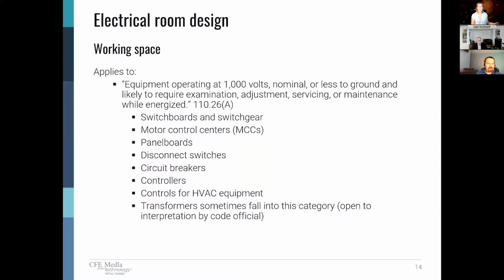So where does the working space requirement apply? Well, 110.26(A) tells us that equipment that's operating at 1,000 volts nominal or less that is likely to be examined, adjusted, serviced, maintained while energized. And that's really the takeaway. That's the part that should probably be underlined and bolded, is the while energized piece. And in practice, that typically is switchboards, switchgear, motor control centers, panel boards, disconnect switches, separately enclosed circuit breakers, motor controllers, controls for HVAC equipment, and sometimes transformers. The transformer is always a discussion. It's almost left open to interpretation by the local authority having jurisdiction. So you've got to be careful about transformers and whether or not you need to provide working clearances in front of that equipment.